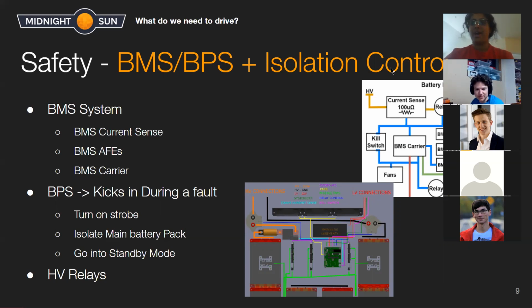Current sense is in the high voltage pack to the batteries, and it measures the current being drawn from the packs at any given moment. Before that, we have conditions we look for in the state of the battery pack before we induce a BPS, our battery protection system: making sure the batteries aren't over-currenting, over-temperature, over-voltage, under-voltage, and over-current in discharge versus charge directions. Current sense measures both current directions and is our point of contact to carrier for those metrics.